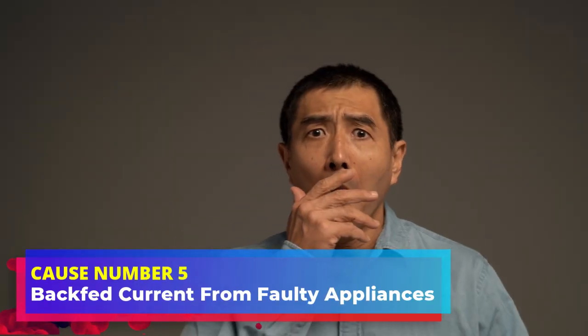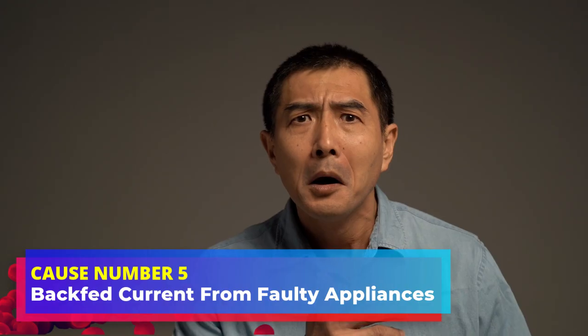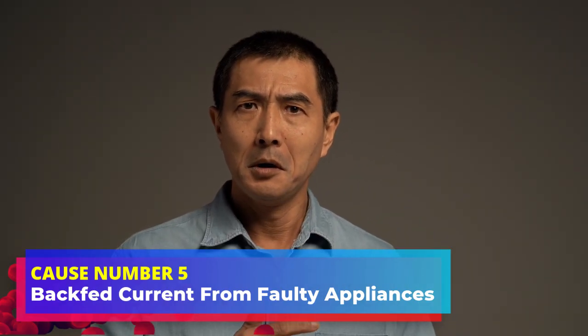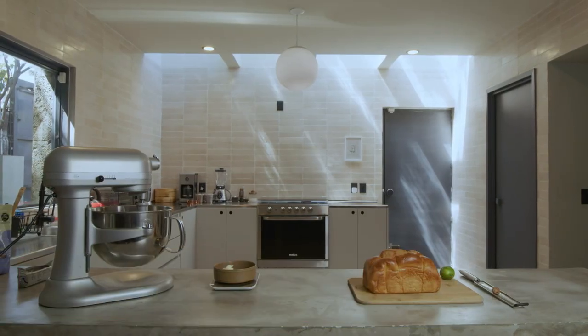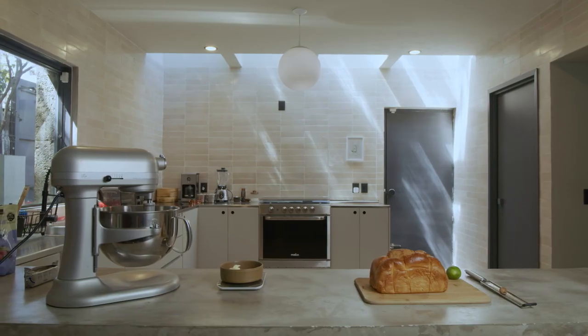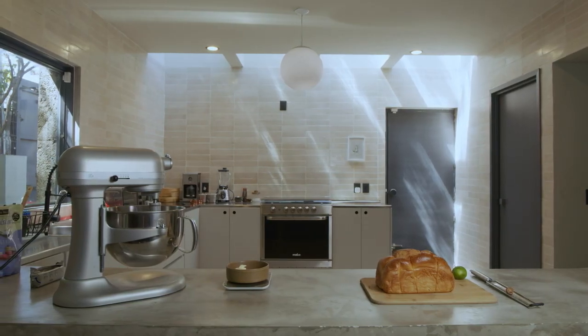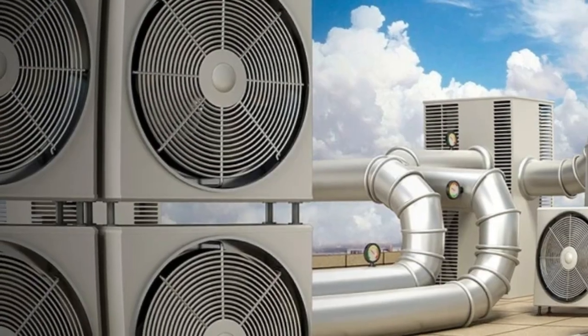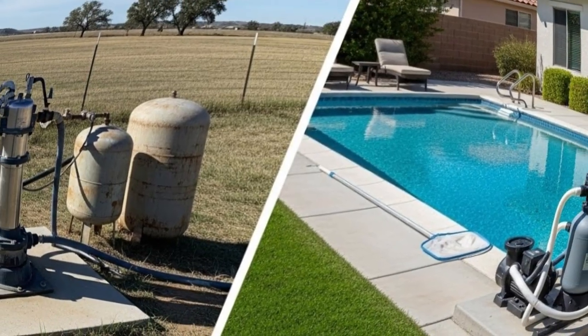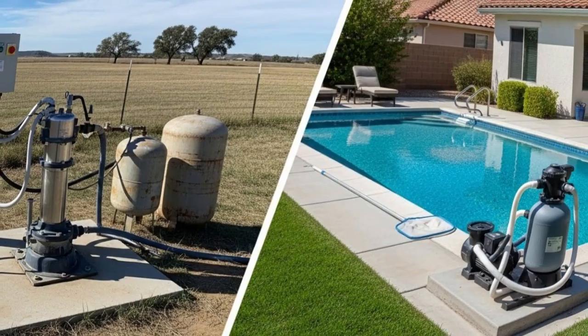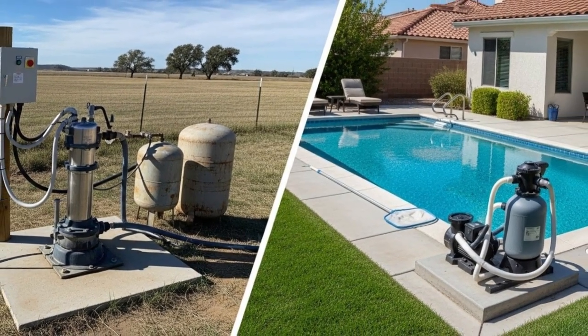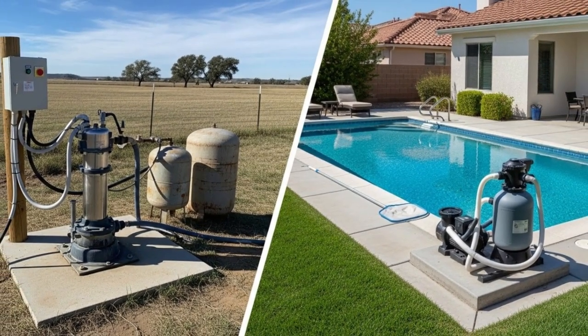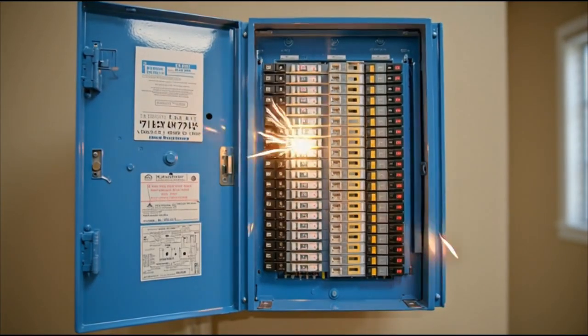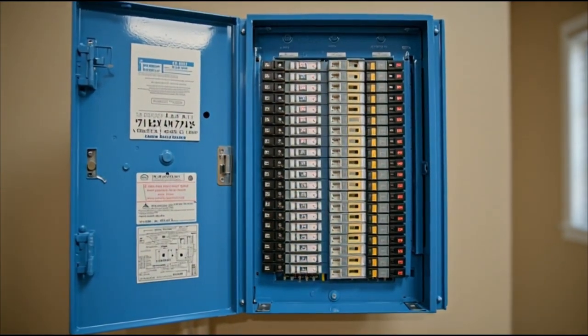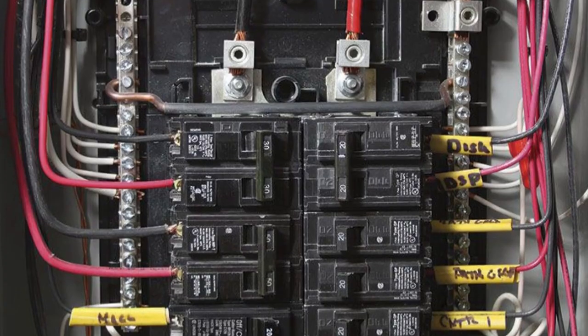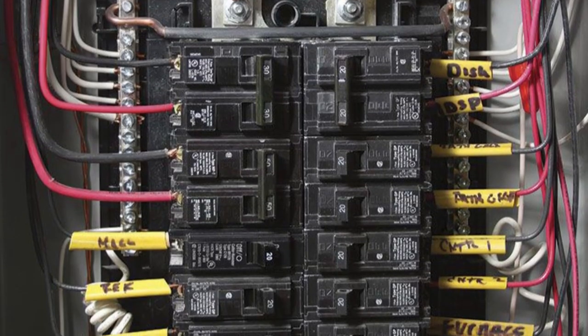This cause surprises most homeowners, but it's more common than you might think. Certain appliances and devices can backfeed current into your electrical system when they malfunction. The most common culprits are older HVAC systems, well pumps, pool pumps, and any appliance with large motors or capacitors. When these devices fail internally, they can create current spikes that travel backward through the circuit, through the panel, and through the main breaker. The main breaker sees this abnormal current flow and trips.